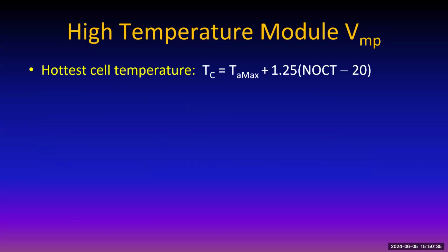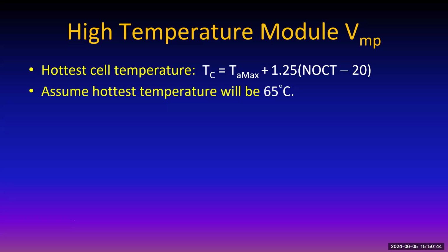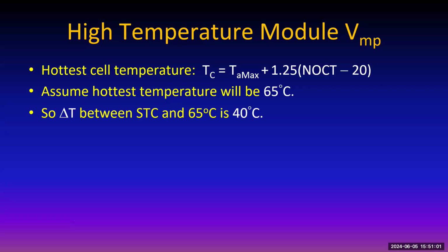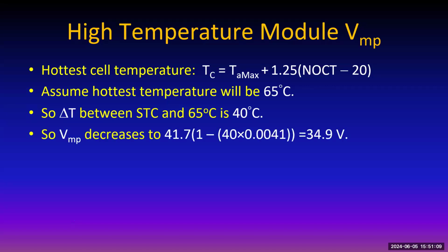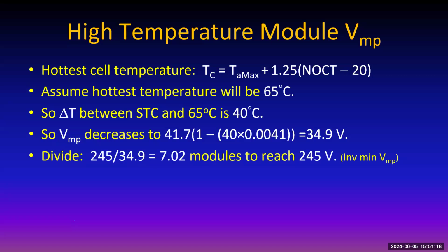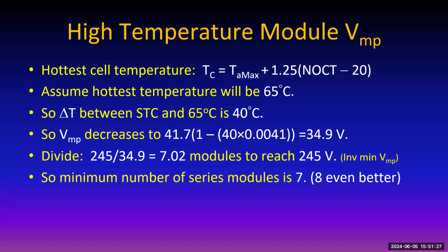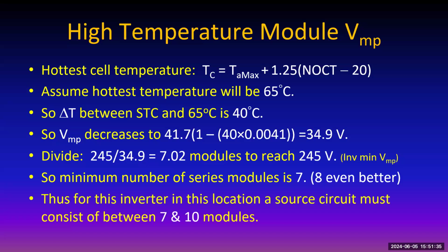So now let's look at the minimum. That's determined by the high temperature and the effect on the maximum power voltage. The hottest temperature might very well be 65 C from the sun shining on the modules. It's not going to be 65 outside, but the module can get up to 65 using this formula right here, starting with the ambient maximum temperature. If it's really at 65, then you've got a 40-degree temperature difference, which means your maximum power voltage will drop to 34.9. 245 divided by 34.9 is 7.02. So you better have 8 of them, because 7.02 is marginally close to that low level. You can do 7, but 8 is a little more comfortable. So that says, gosh, 7 to 10 modules.